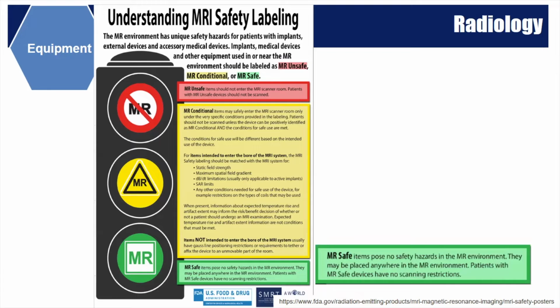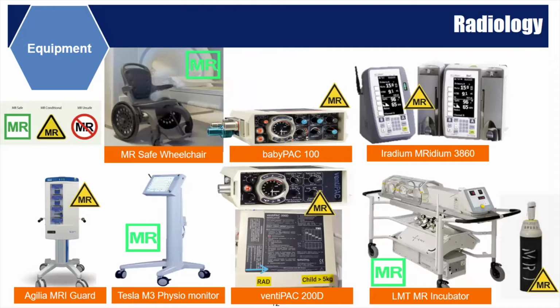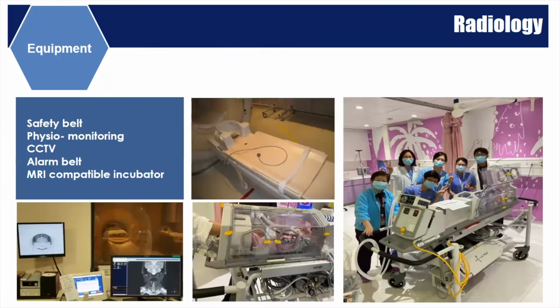MR safe items pose no safety hazards in the MR environment. They may be placed anywhere in the MR environment. Patients with MR safe devices have no scanning restrictions. These are the items we commonly use. For example, we have MR safe wheelchair. Our physio monitor is also MR safe, and these equipment can be brought very close to the MR bore. However, we need to observe the 150 Gauss line when using our ventilators. In addition, there are other equipments that ensure patient safety while in the scanner, for example, safety belts, CCTVs, alarm belts, and we also have an MRI compatible incubator.